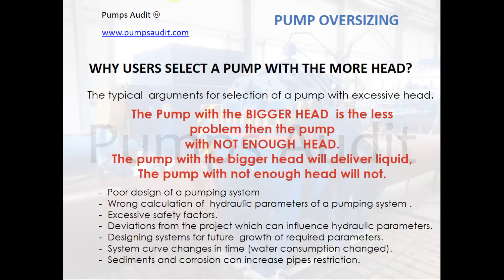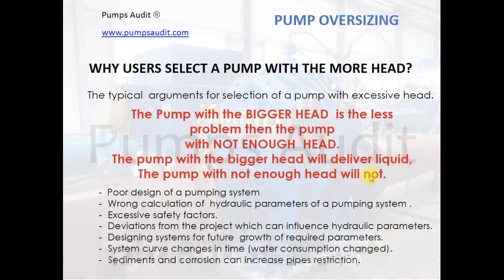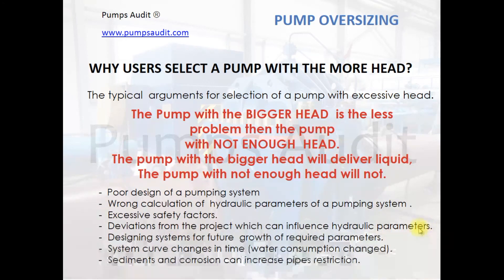Why do pump users select a pump with more head? The most popular answer is that a pump with a bigger head is less of a problem than one with insufficient head — the pump with bigger head will deliver liquid, while the pump with insufficient head will not. There are different reasons for selecting pumps with bigger parameters: poor design of a pumping system, wrong calculation of hydraulic parameters, excessive safety factors, deviation from the project which can affect hydraulic parameters, designing a system for future growth, changes in system curve over time such as changes in water consumption, and sediments and corrosion which can increase pipe restriction.